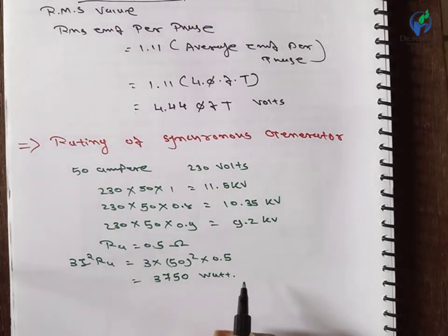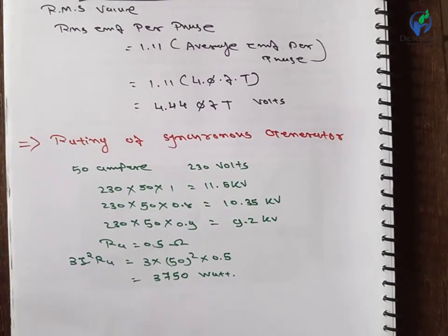This is the same in all cases, so the copper loss is not dependent on power factor, though the output power of the alternator is different. The copper losses cause the temperature rise of the alternator and ultimately decide the rating of a synchronous generator.